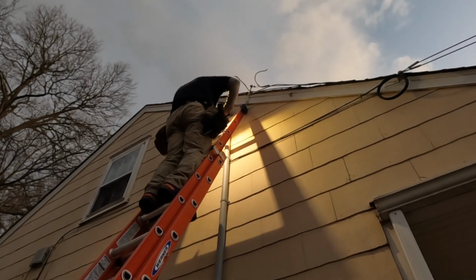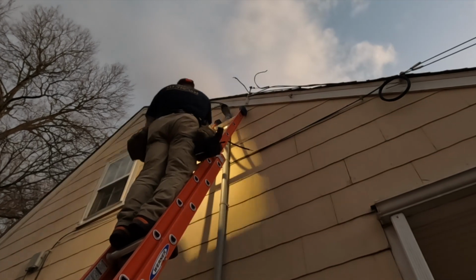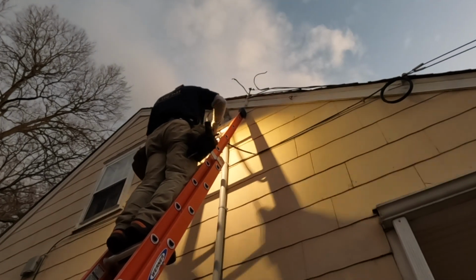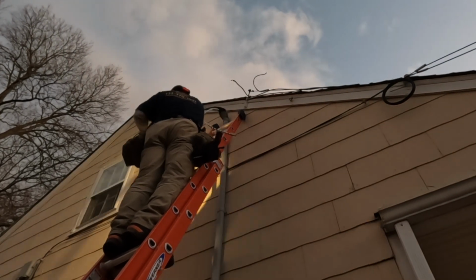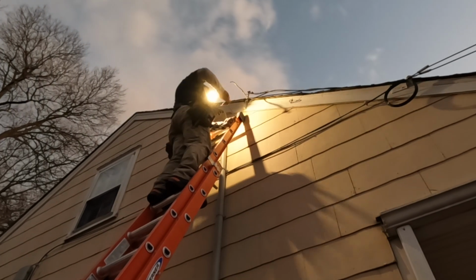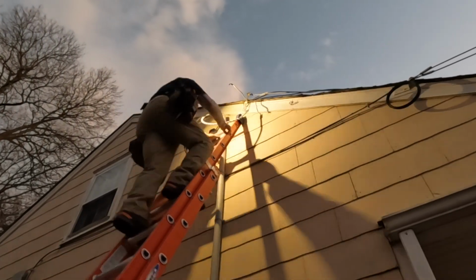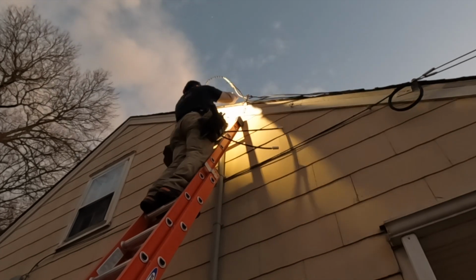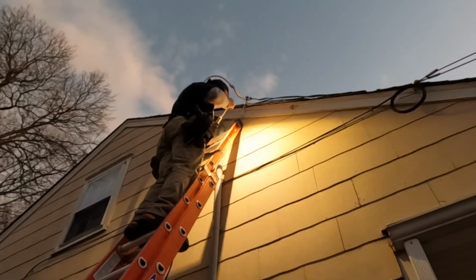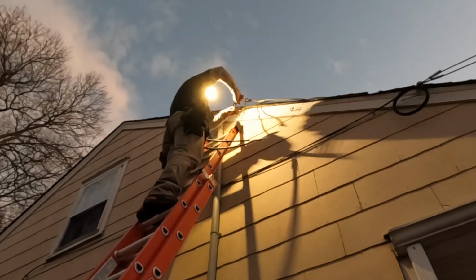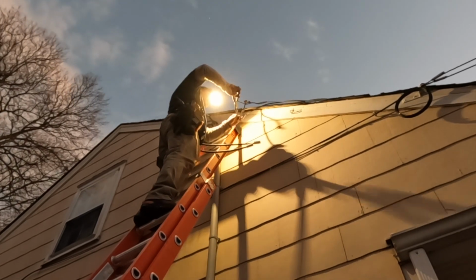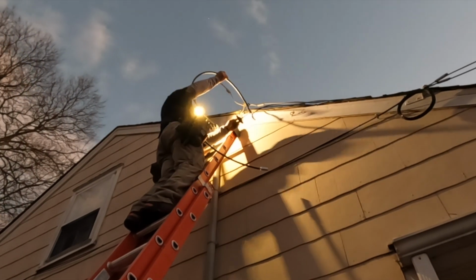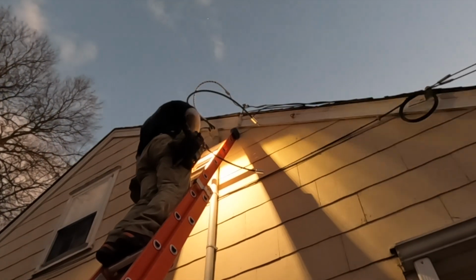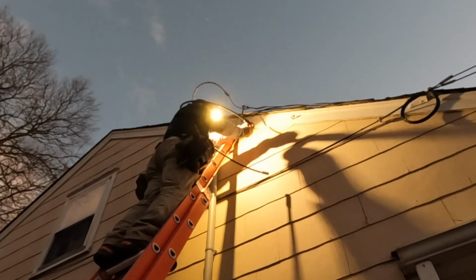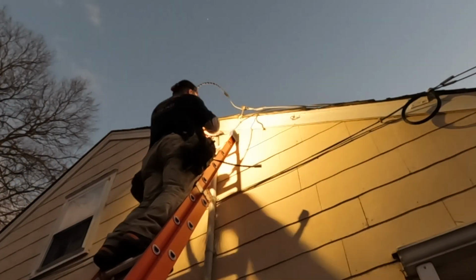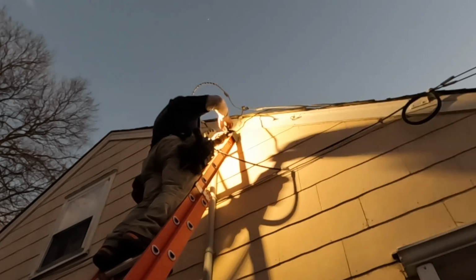Obviously, I'm up on my extension ladder here, and I'm reconnecting to the utility. I use butt splices here to connect back to the utility. I'm told by some people that they're not rated for outdoor use, and other people say, nah, you're fine. PSE&G drops off these connectors to me sometimes. I don't know how they use them because they're not large enough for 4/0 aluminum. They're good for number 2, but not for number 4/0 aluminum. So usually when they give them to me, I toss them, and I use the butt splices.